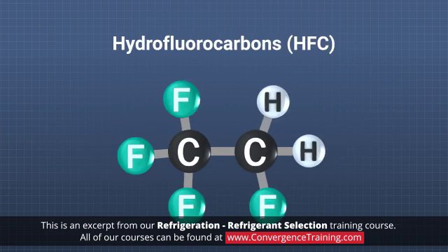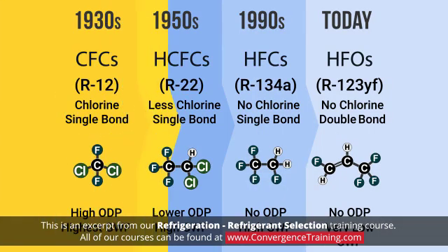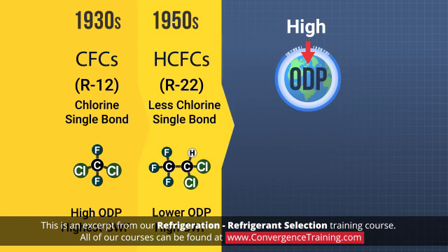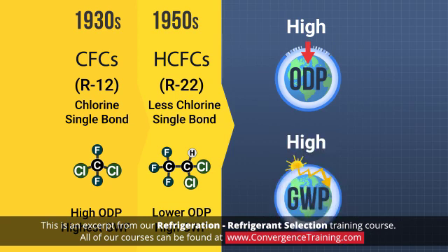And hydrofluorocarbons, or HFCs, which contain hydrogen, fluorine, and carbon. CFC and HCFC refrigerants were widely used in the 20th century because they are relatively inert, non-flammable, and non-toxic, which make them much safer than early refrigerants like ammonia, sulfur dioxide, and methyl chloride. However, CFCs and HCFCs are being phased out because it was discovered that they have both high ozone depletion potential, or ODP, and high global warming potential, or GWP.